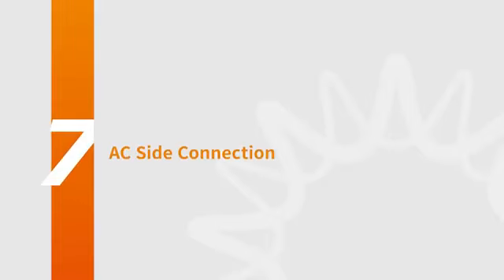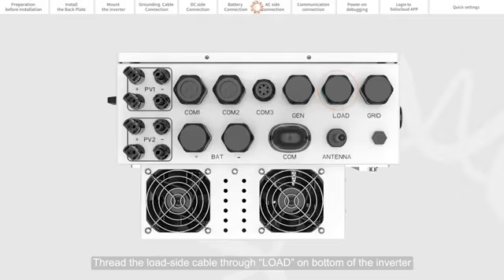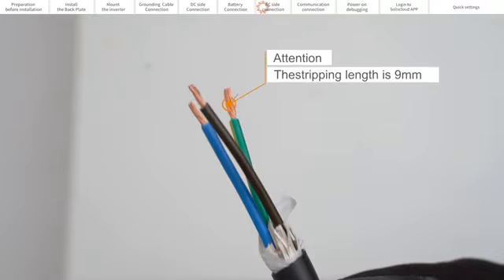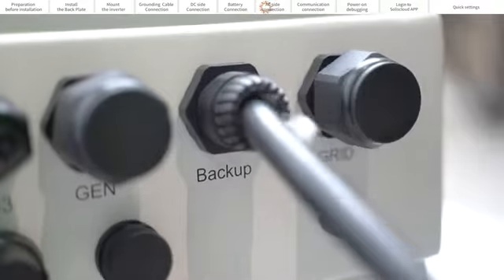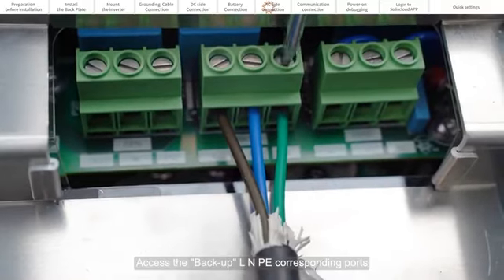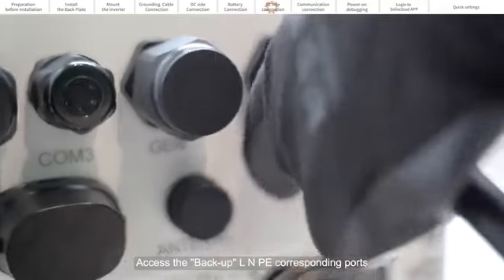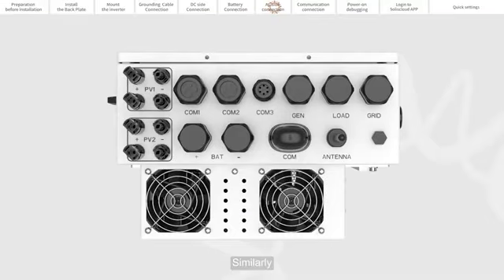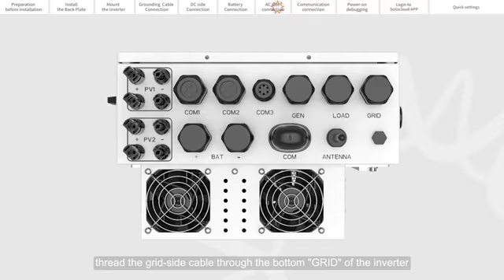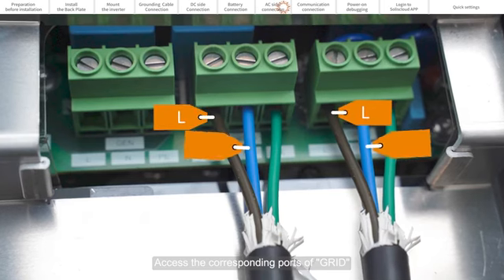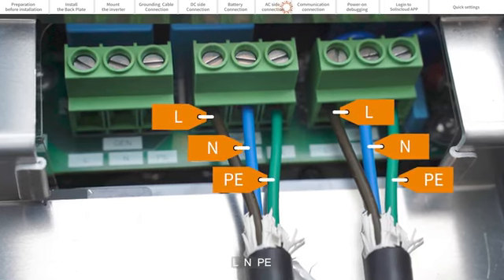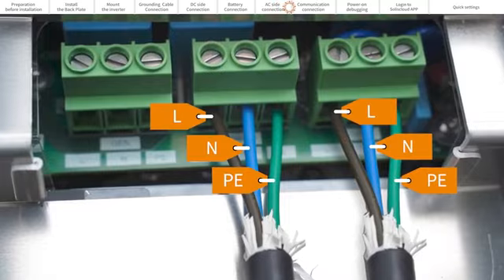Part 7. AC side connection. Pass the load side cable through the LOAD opening on the bottom of the inverter and connect the backup line, neutral, and earth to the corresponding ports. Similarly, pass the grid side cable through the GRID opening at the bottom of the inverter and connect the grid line, neutral, and earth to the corresponding ports.